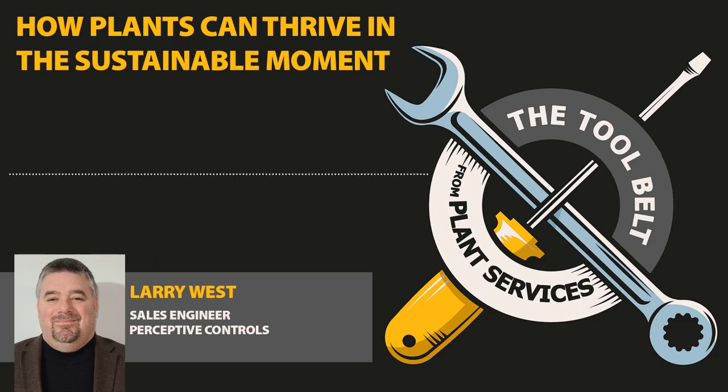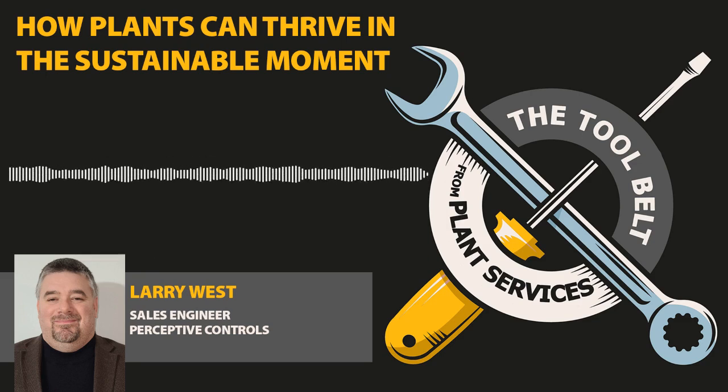When we talk about energy savings, the same thing applies. So if I have a conveyor that runs in the morning at 3.2 amps, but in the afternoon it runs at 4.8 amps, what changed? Am I getting more production? Am I not? And I can see those numbers. And if I'm not getting more production, then I know something has changed. We don't know what that is, but that gives me the point of the investigation to do. Without that data coming back, it's out of sight, out of mind. It's that conveyor running in the corner with nobody looking at it. And that's what SCADA can do.